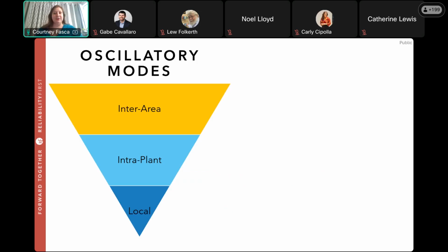So basically, to break that down, what we have are called local modes of oscillations. So these are small, as it implies, a local generator oscillating against the rest of the system. This is a single biker who is getting out of sync with the rest of the bike, pedaling a little slower, maybe they're getting tired. And in reality, this mode has a limited geographic extent, usually 50 to 100 miles. So a grid example would be that a generator at a power plant oscillates against another generator at the same plant or against the local transmission network.